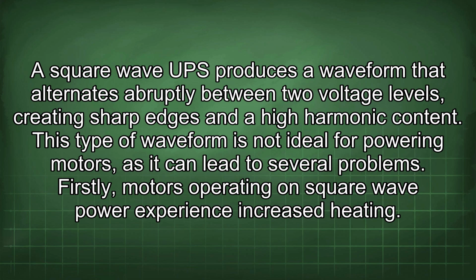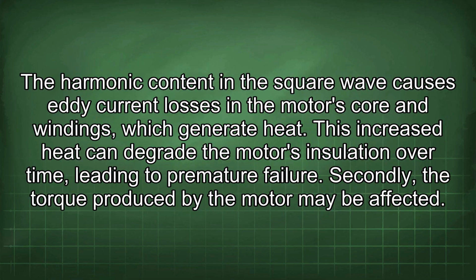Firstly, motors operating on square wave power experience increased heating. The harmonic content in the square wave causes eddy current losses in the motor's core and windings, which generate heat. This increased heat can degrade the motor's insulation over time, leading to premature failure.